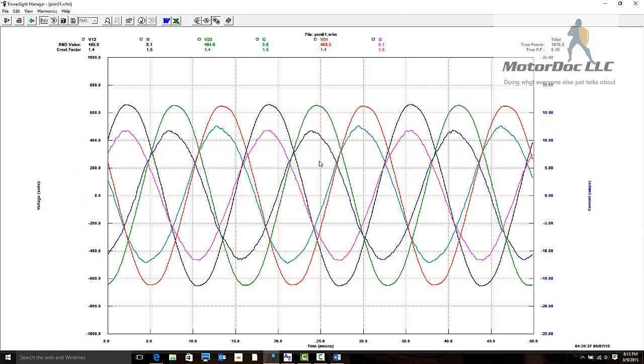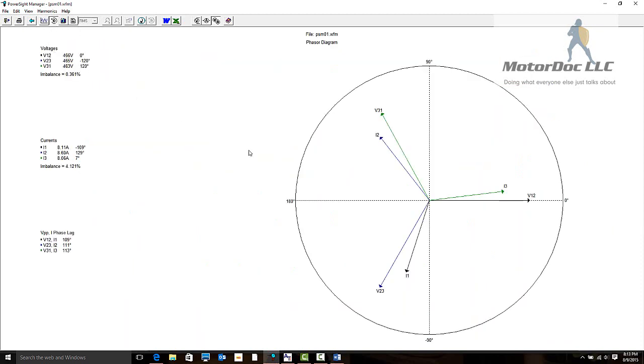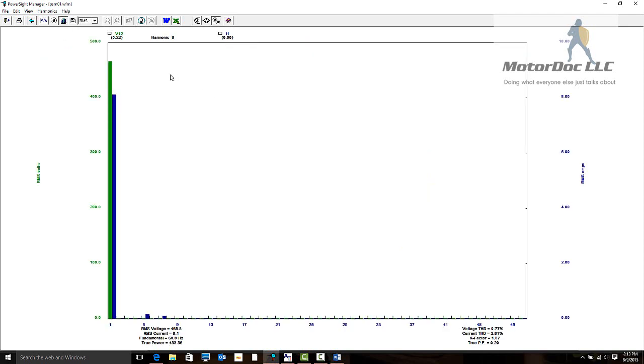I've got both my voltage and my current in here. This is the current on this side and this is the voltage on this side. The voltage looks a little dirty. The other thing we can do while we're in here is take a look as well at the phasor diagram to make sure everything's nice and balanced, as well as harmonics. Here's our power harmonics in both voltage and current. They've got a slight fifth and seventh, even though this is not on an inverter.